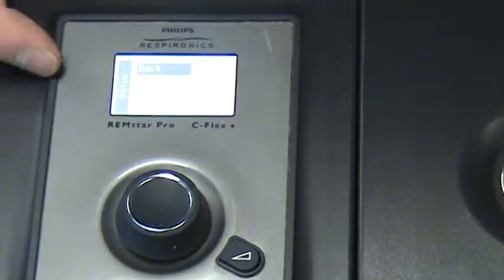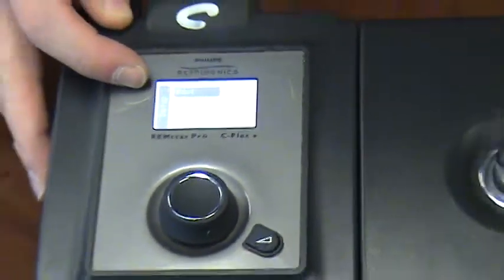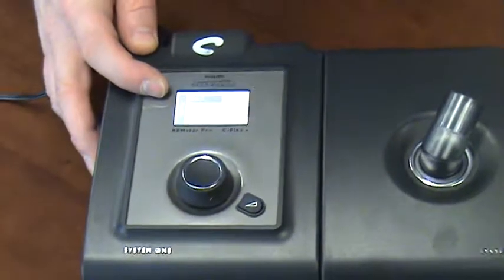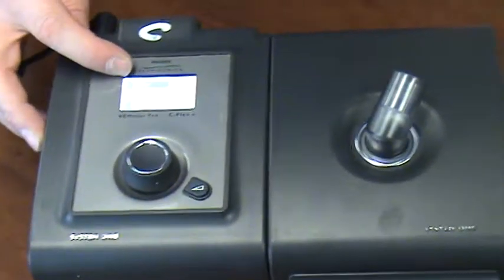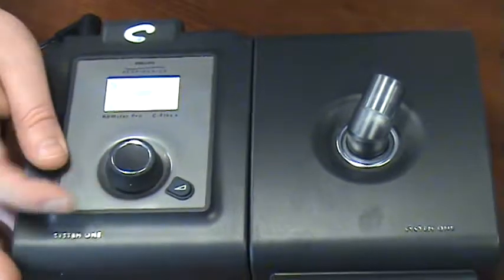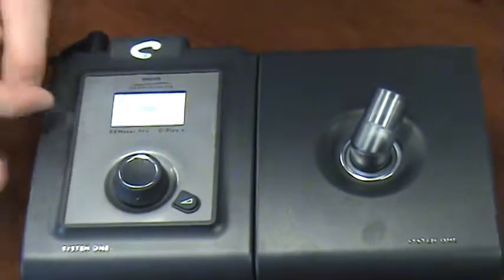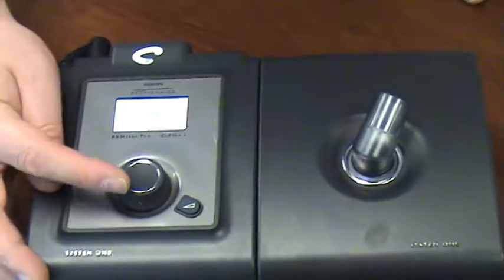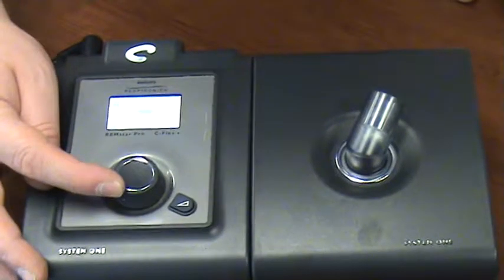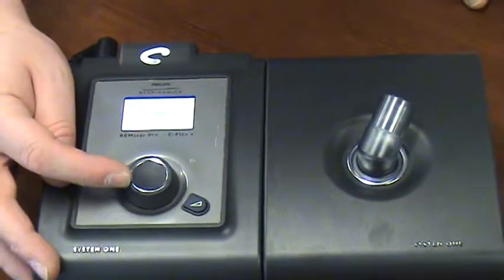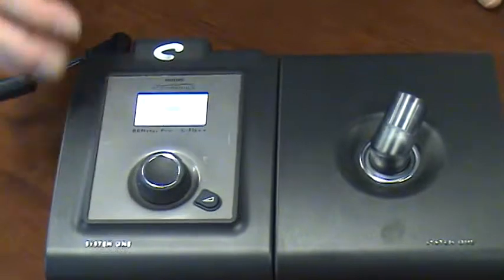Now this is actually a CPAP. CPAP, BiPAP setup on all these devices are identical. BiPAP obviously has 2 settings versus CPAP has 1. So in this here, the word back is highlighted. I can scroll down to mode. If I were to select mode, the word CPAP is highlighted. I can actually set different types of CPAP on here, which we're not going to mess with.